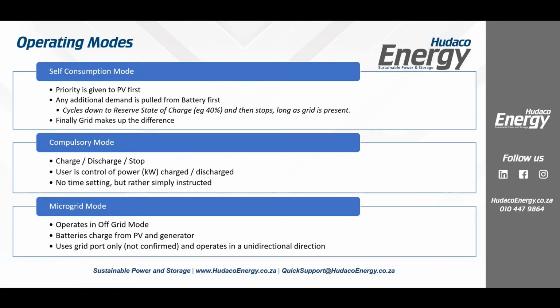And then finally, we have mini grid mode, or microgrid mode, as they call it. In here, we operate in off-grid mode. We do this when there is no grid connected. In other words, there is no Eskom. We're running on a farm or something like that. And the nice thing is it gives us the opportunity also to bring a generator in. So we can run a generator on that mains port as well. And we can use that to charge, discharge, backup, do whatever else we need. And we can run completely without it. What we do is we allow the inverter then to form the grid on both ports.